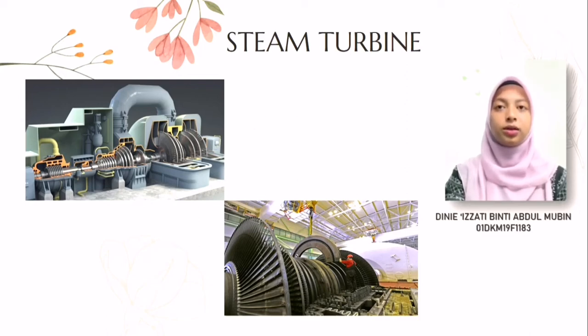First, condensing turbines are most commonly found in electrical power plants. These turbines receive steam from a boiler and exhaust it to a condenser. Second, non-condensing or back pressure turbines are most widely used for process steam application, in which the steam will be used for additional purpose after being exhausted from the turbine. The exhaust pressure is controlled by a regulating valve to suit the needs of the process steam pressure.